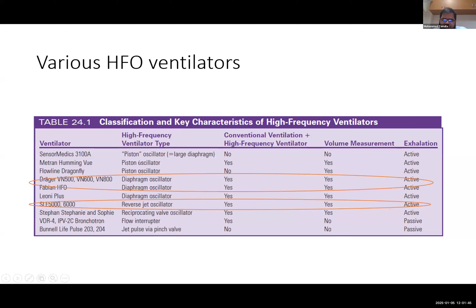So there are various different mechanisms. A few studies have shown that ventilators vary in the delivery of delta P and pressures. Whatever we have set, the delivered pressures will differ on the babies depending on the type of ventilator you are using. There are minute variations too. I have not kept the images, but these are just the names: Sensormedics, Drager, Fabian, SLE, and Bunnell. The hybrids let you use both high frequency and conventional ventilation. Sensormedics is only a standard high frequency ventilator, with no conventional ventilation. The Bunnell Life Pulse is only for high frequency jet ventilation; you can't give both. Exhalation is passive with jet ventilation, while with the oscillator it is active, because we are using a diaphragm or a piston as the mechanism.